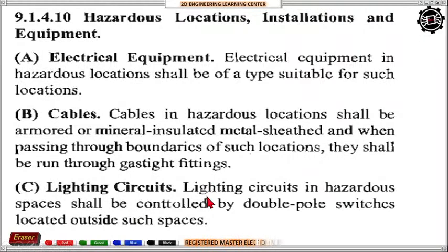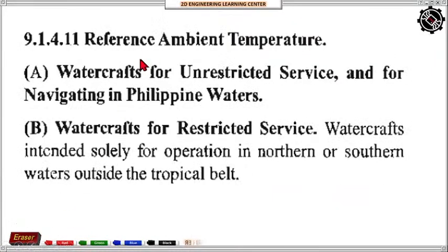Okay, so lighting circuit in hazardous spaces shall be controlled by a double pole switch located outside such spaces. So reference ambient temperature. So watercrafts for unrestricted service and for navigating in the Philippine waters. So the reference ambient temperature is the normal temperature sa ating mga oceans. Watercraft for restricted service. So watercrafts intended solely for operation in northern or southern water outside the tropical belt.